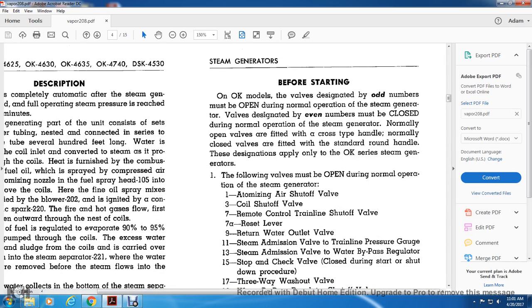Before starting, the OK steam generator valves designated with odd numbers must be open during normal operation. Steam generator valves designated with even numbers must be closed. During normal operation, the normally open valves are fitted with a cross-type handle. The normally closed valves are fitted with a standard round head handle. This designation applies only to the OK steam generators.